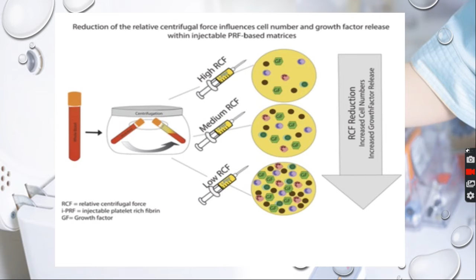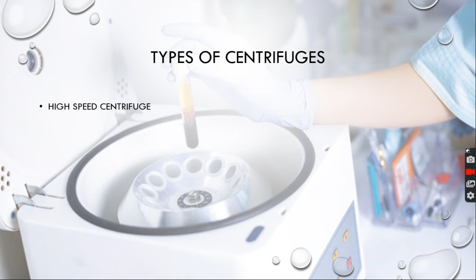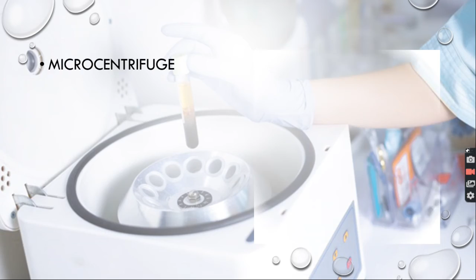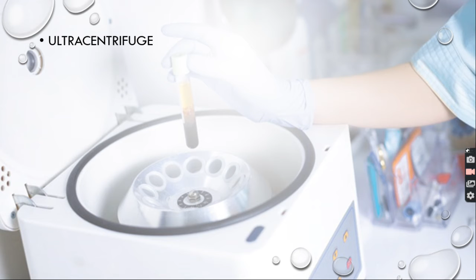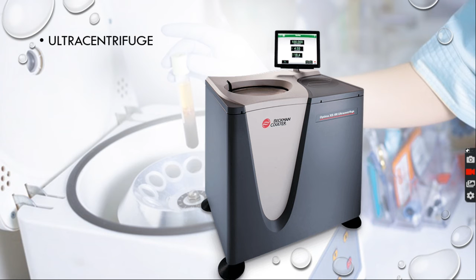Types of centrifuges. Number 1 is the high-speed centrifuge. High-speed centrifuges spin at a speed of 15,000 to 20,000 rpm and usually have a large sample capacity. This is the diagram of a high-speed centrifuge. Next is the microcentrifuge. Microcentrifuges spin at 12,000 to 13,000 rpm and take up to 2 ml volume. It is small enough to fit on a tabletop. You can see its diagram. The last one is the ultracentrifuge. Ultracentrifuges spin at 65,000 rpm and are able to isolate particles like ribosomes, proteins and viruses. It is very expensive. This is the diagram of an ultracentrifuge.